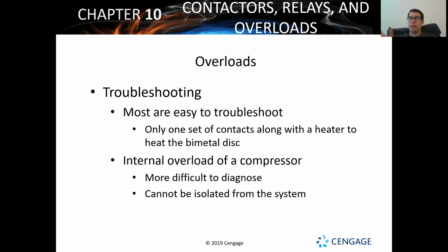So I've seen guys do this. I've had it before where they've gone and diagnosed a bad compressor. Let's get a new one. They're under warranty. It's going to be no cost. It's going to be no problem. And they get out there, they take out the old compressor, put in the new one, the system starts right up, cool, they get out of there, and then they get called back to the office about a week later. Now, they're not getting called back to the customer's house because the system's working, it's fine, they replaced the compressor.